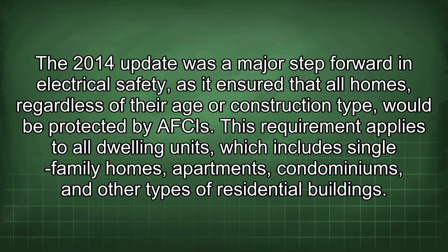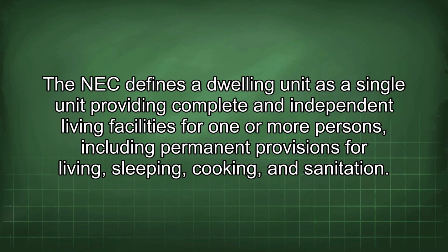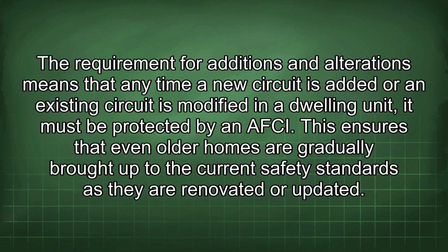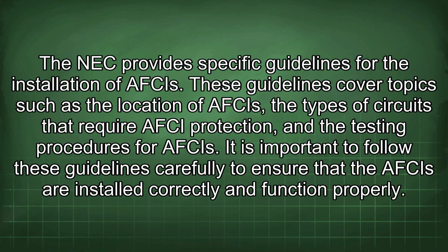This requirement applies to all dwelling units, which includes single-family homes, apartments, condominiums, and other types of residential buildings. The NEC defines a dwelling unit as a single unit providing complete and independent living facilities for one or more persons, including permanent provisions for living, sleeping, cooking, and sanitation. The requirement for additions and alterations means that any time a new circuit is added or an existing circuit is modified in a dwelling unit, it must be protected by an AFCI. This ensures that even older homes are gradually brought up to the current safety standards as they are renovated or updated.